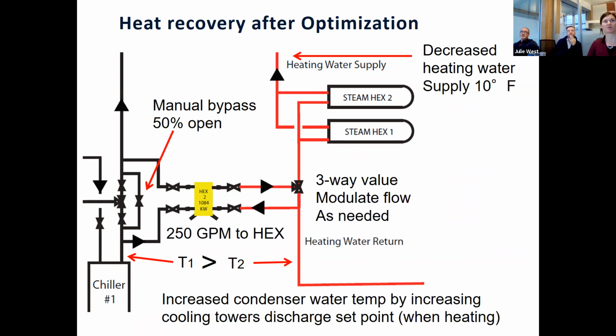And then the other problem we found was that there was a manual bypass that was 50% open. So even if we wanted to change the temperatures and lower the return water temperature from the building, we had to close this bypass in order to actually force flow through this heat exchanger. We were also able to increase the condenser water temperature on our BMS system. And so then we were able to reject heat into the heating water system. So we decreased the heating water supply by about 10 F, which then decreased the return water temperature and also increased it on the condenser water side so we could actually reject heat.